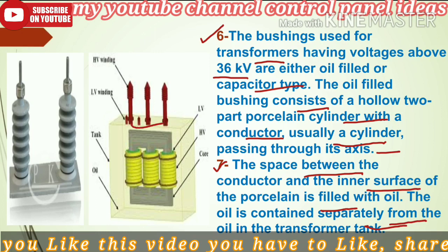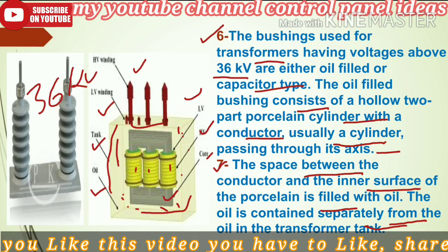This is the complete transformer, this is the core, inside is the LV coil, outside is the HV coil. This is a three-phase transformer. This is the HV bushing, this is the LV bushing, this is the tank, and inside is oil. This is a 36 kV bushing.